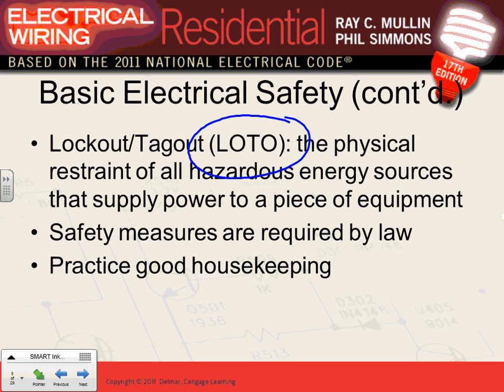That's the rule. The exception is working on things energized. When you work on things energized, by 70E you have to have an energized work permit. Tons of people have to sign it, and you have to verify why you need to work on it. So it's a big deal.